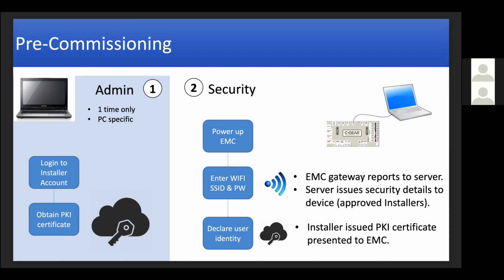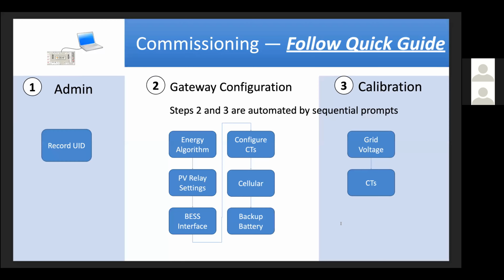The EMC would report to the server, and it would download the list of certificates, as I just mentioned, of all of the approved installers who are allowed to access that device. That installer-issued PKI certificate is presented to the EMC, and then access is granted to configure the system. As far as onboarding your device, you would record the device UID, which is given with each new system out of the box, as well as the customer name and address and email for monitoring. You would record all that stuff when you onboard the device.